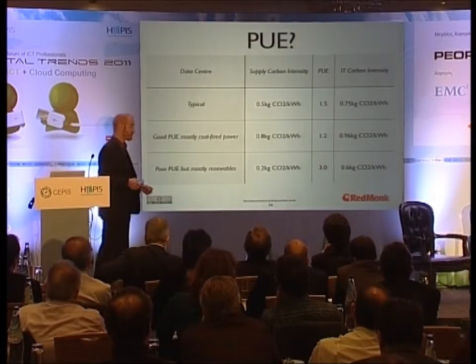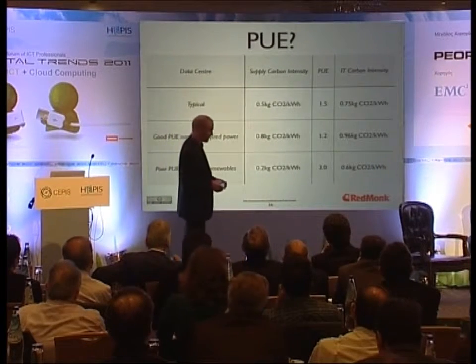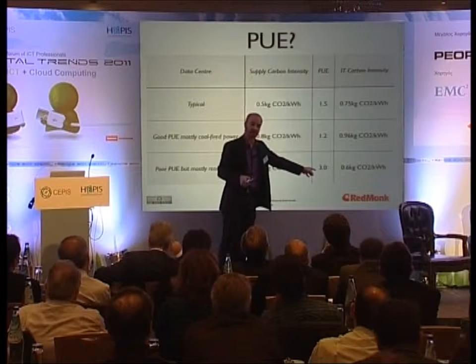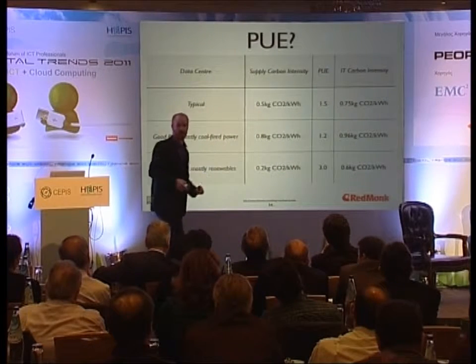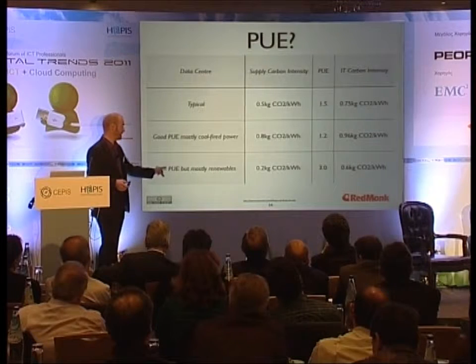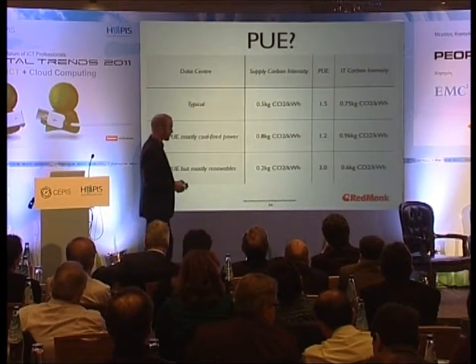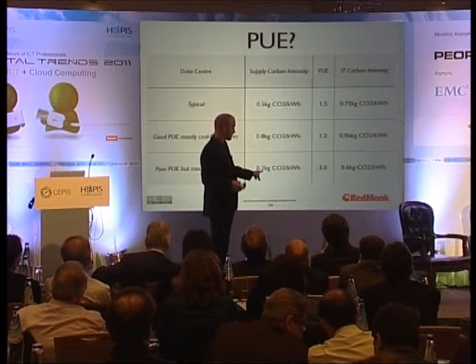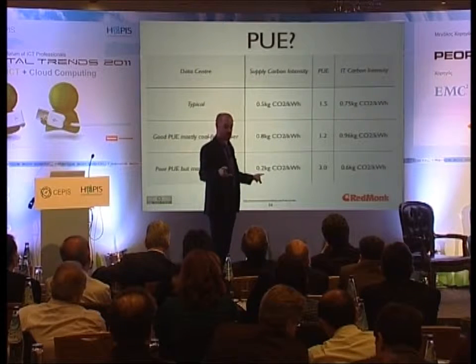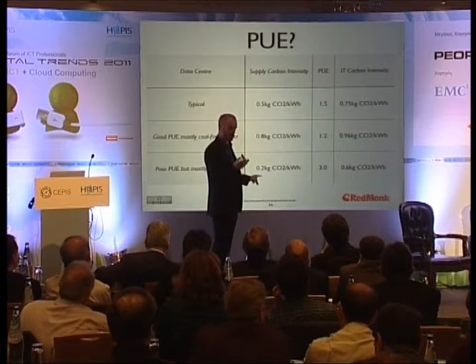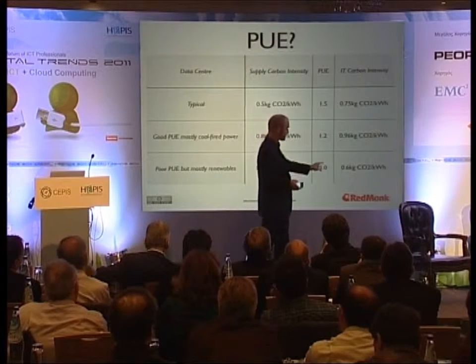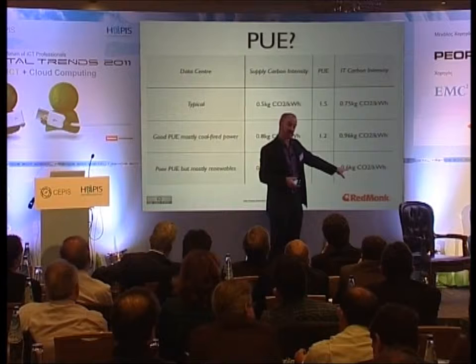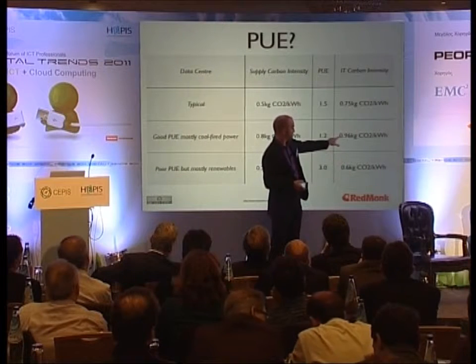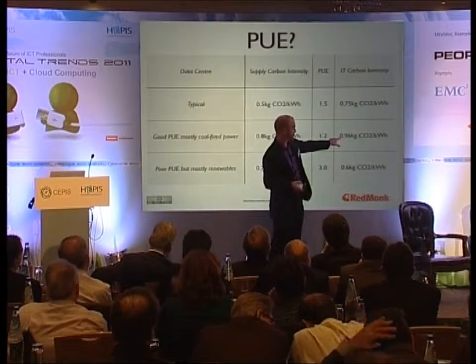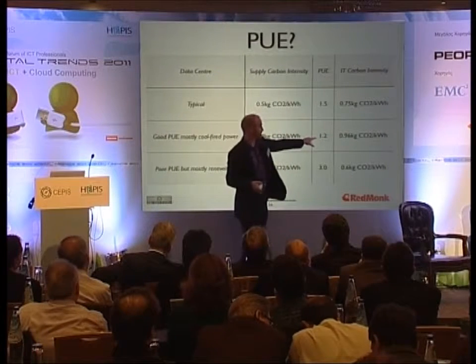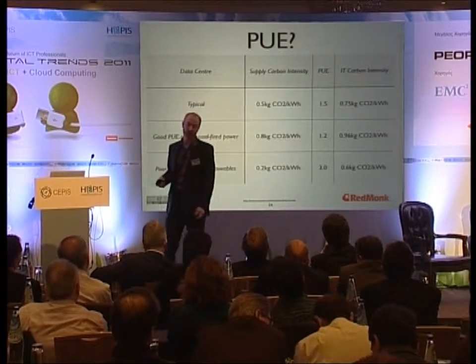On the other hand, if you've got a really bad data center with a PUE of 3, very inefficient, but fired mostly by renewables, so your supply carbon intensity is 0.2 — still significant, there's carbon being produced — 0.2 times 3 gives you 0.6, which is significantly less. It's 60% of the carbon intensity of the data center with a PUE of 1.2.